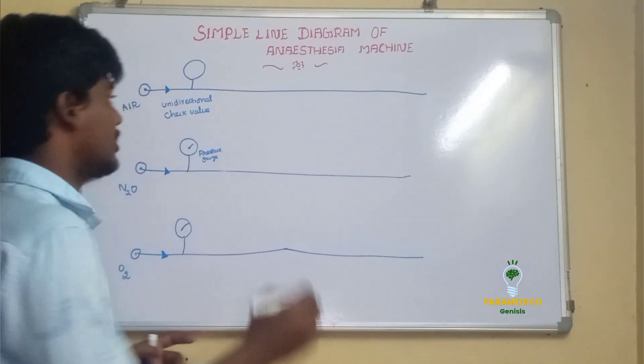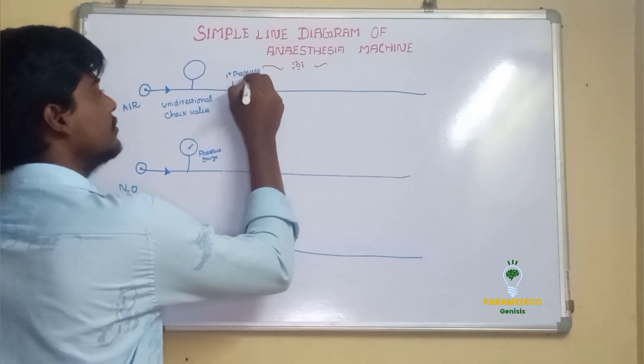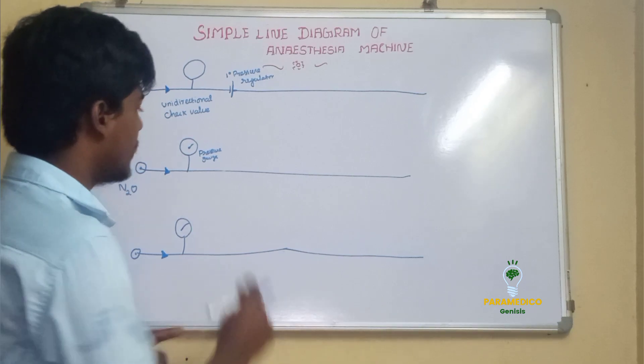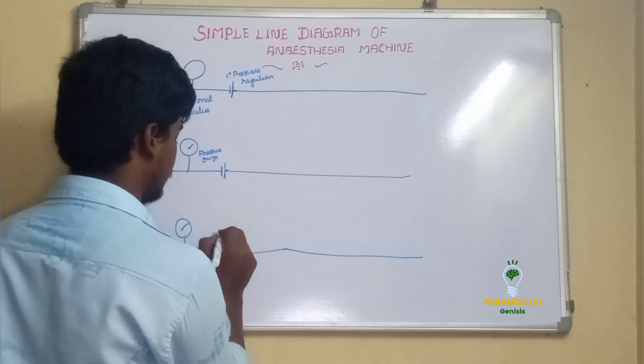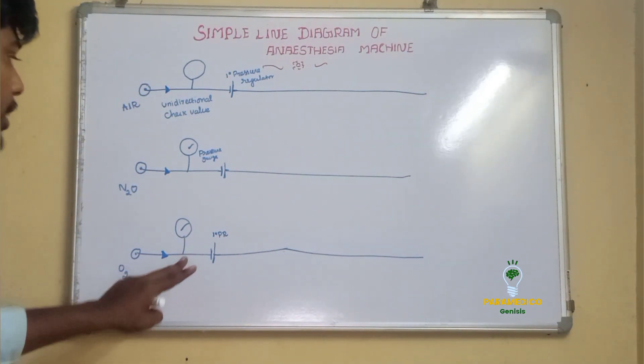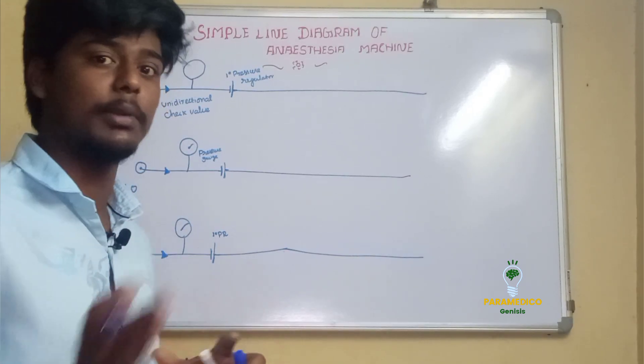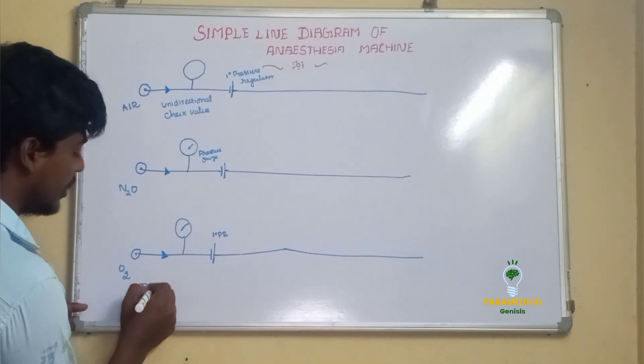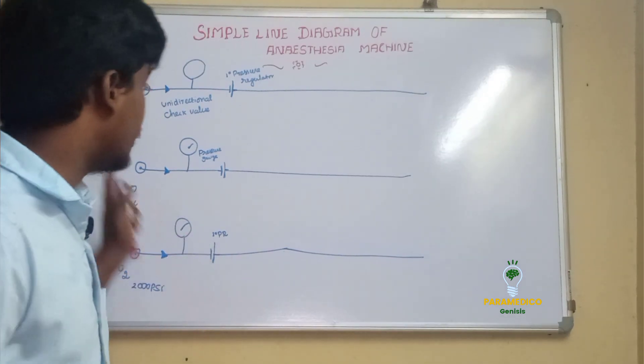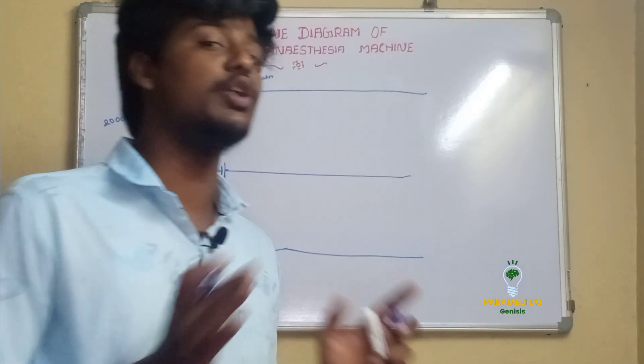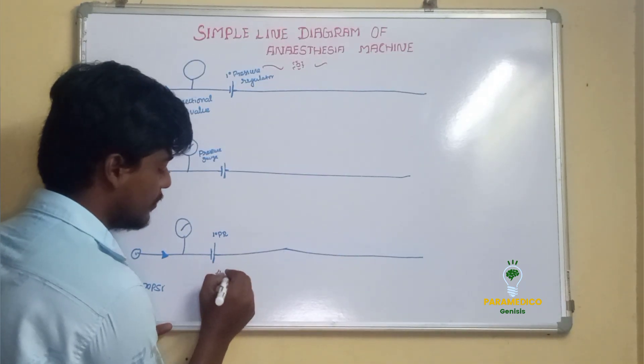After the pressure gauge, the very important structure is called the primary pressure regulator. The primary pressure regulator is present in all three lines. It helps to reduce the pressure of the medical gases. Oxygen has a pressure of 2000 psi, nitrous oxide has 760 psi, and air also has around 2000 psi — these are very high pressures. The pressure regulator reduces these pressures down to 45 to 60 psi.